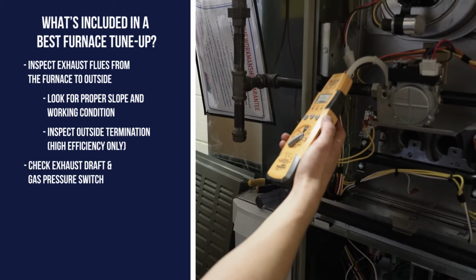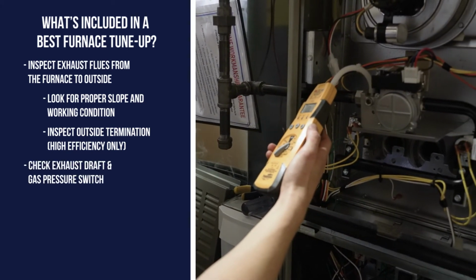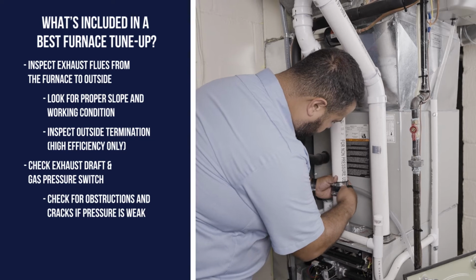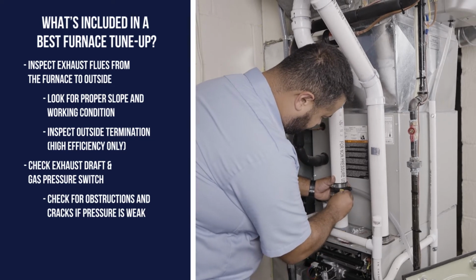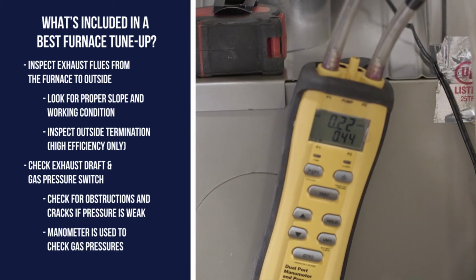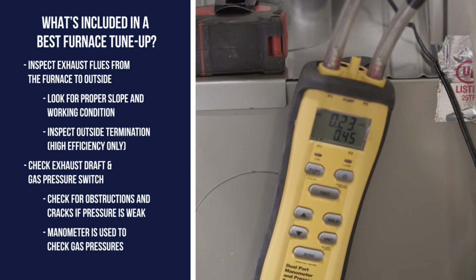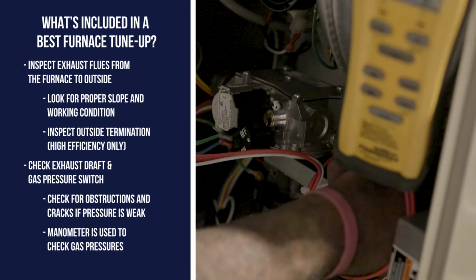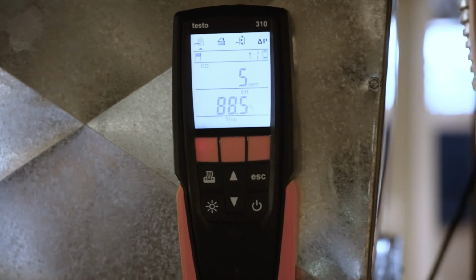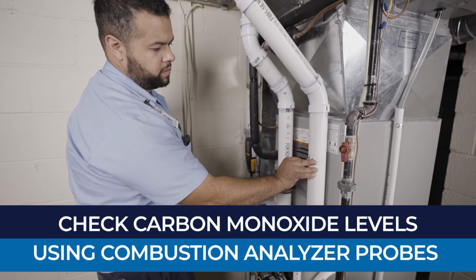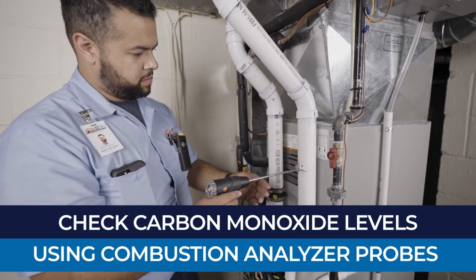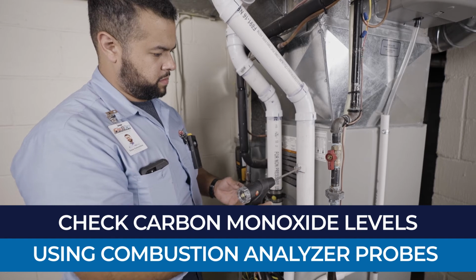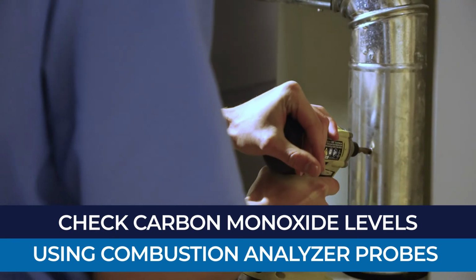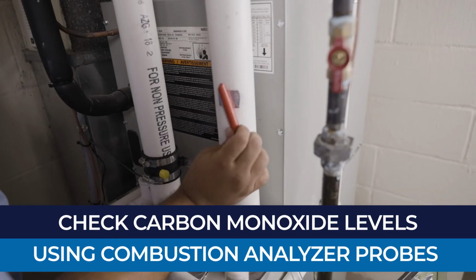Next, we'll turn the furnace back on and check the exhaust draft and pressure switch. If the draft is weak, we check for any obstructions and cracks in the tubing. Next, we check the gas pressure with a manometer to ensure the gas pressures are to the furnace's specifications. We will make the proper adjustments if any are needed. One of the last but most important steps we do is check carbon monoxide levels to make sure they are within normal levels. We check by inserting a combustion analyzer probe in both the supply air duct and the exhaust pipe through a 1/4 inch hole. If a hole isn't present, one will be drilled and later sealed.